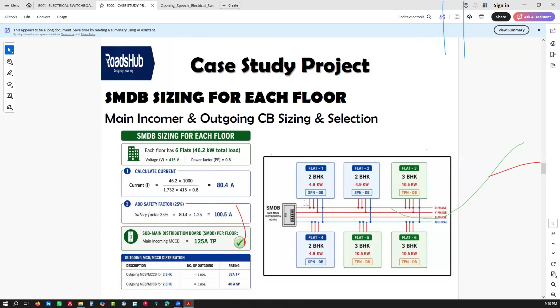So if you now know that this is the value, 125, that you need for each SMDB, it's easier for you to select one. So we said we have 32 amps, 32 amps, 32 amps going to the 3 BHKs. And then we have 40 amps, 40 amps. This one was a single phase system. This one was a three-phase system. So for this representation, we selected an SMDB, which is a sub-mains distribution board that is going to supply a TPN DB on the 3 BHK. I didn't include the 2 BHK because you will tap from the 32, you go to the first. This is per floor, so you need 6 SMDBs.